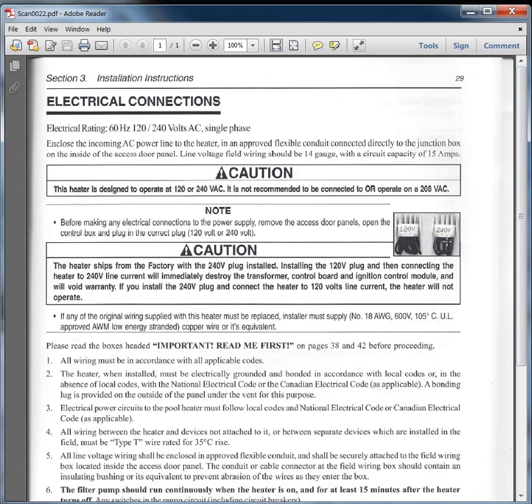Again, also, it comes pre-wired for 240. If you don't read and understand your manual, the common thing is if you hooked it up to 120 and it's pre-wired for 240, a service system light will turn on very dimly, and the heater will not turn on.